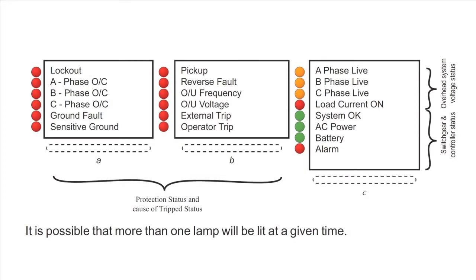ADVC2 status lamps. A brief explanation of the function and meaning of the various status lamp LEDs will help to clarify the understanding of the operator interface. In the first column, there are 6 LED status lamps. Lockout. Recloser has tripped to lockout due to a protection sequence or operator command. Automatic close operations are not possible, and the operator has to close the recloser using the control panel or a remote command. The LED is red when activated.